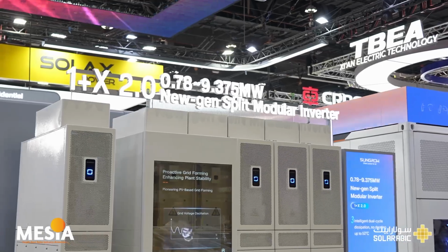When we look at the 1+X 2.0 inverter, it is a modular design, so it can provide granular power management. What this means is that when the data center loading is ramping or fluctuating between the training and the inference status, we can dynamically activate and deactivate the modules of the individual 800 kilowatt inverters. So it ensures the active inverter is always running at its optimal peak efficiency, rather than relying on a big centralized inverter, which is always running at half or partial load, which is not that efficient. Very interesting.